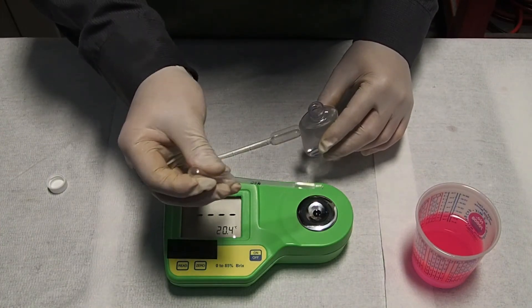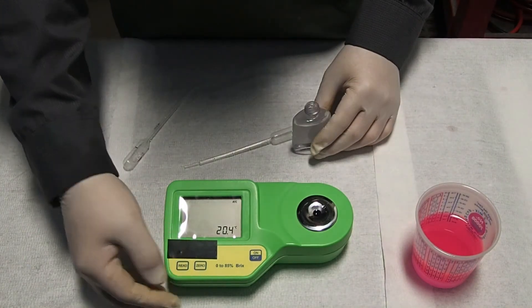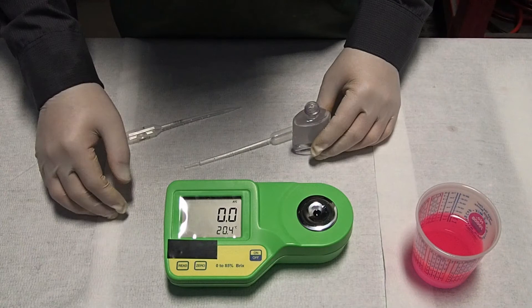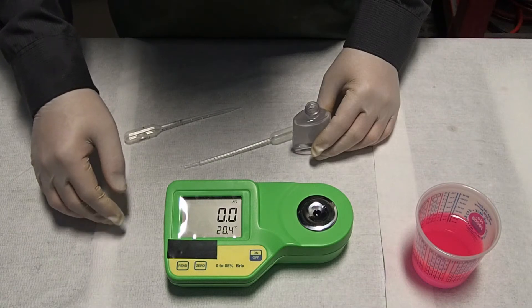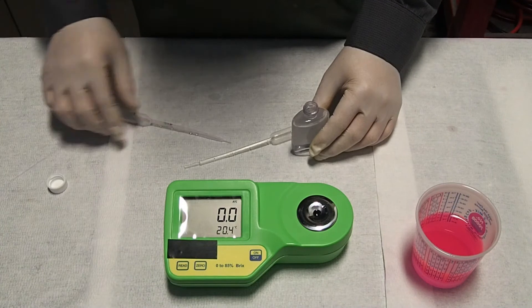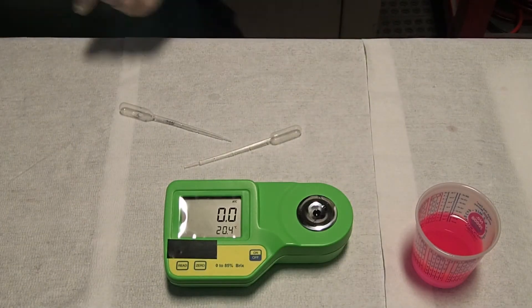We are going to push the read key and the instrument gives us zero percent. This zero percent means that the reference point is set. If not, if we have a different value, we are going to push the zero key and automatically the refractometer will take this reference point.